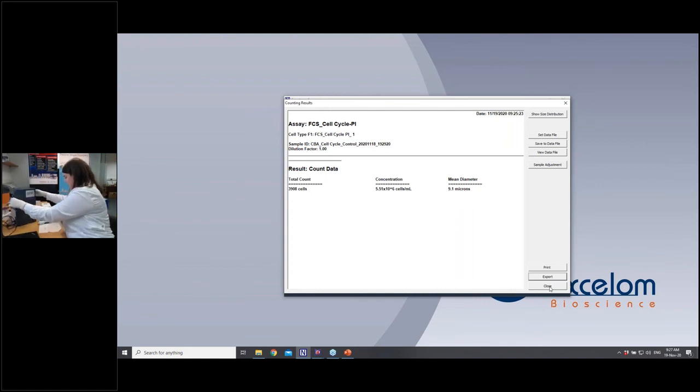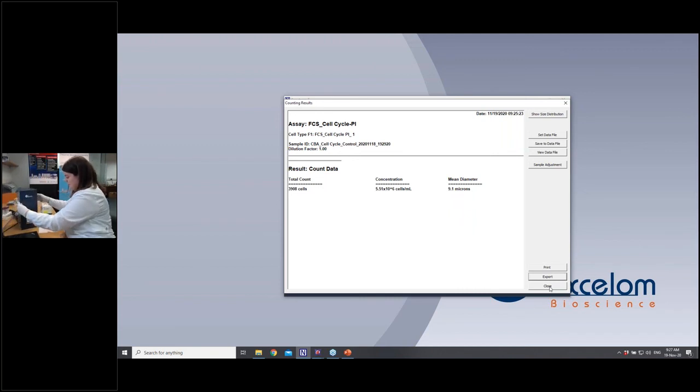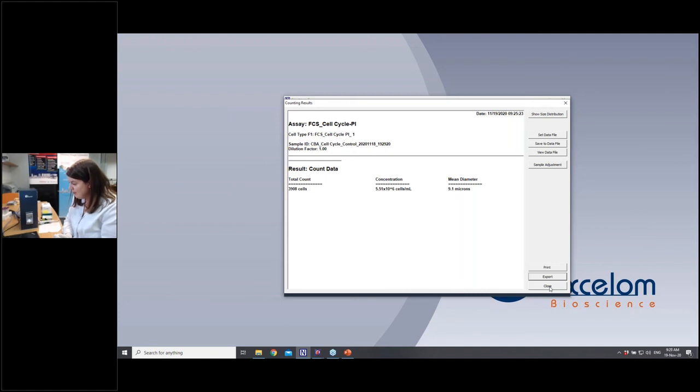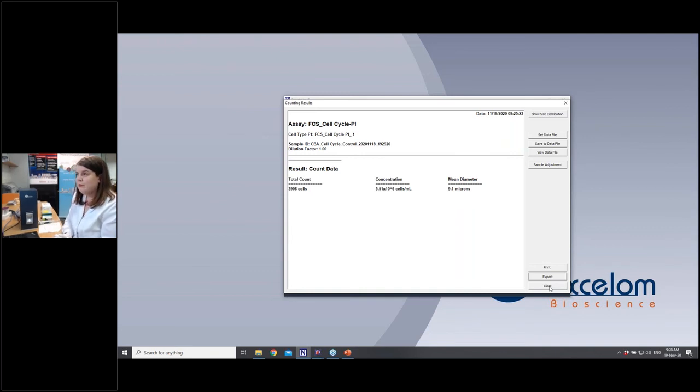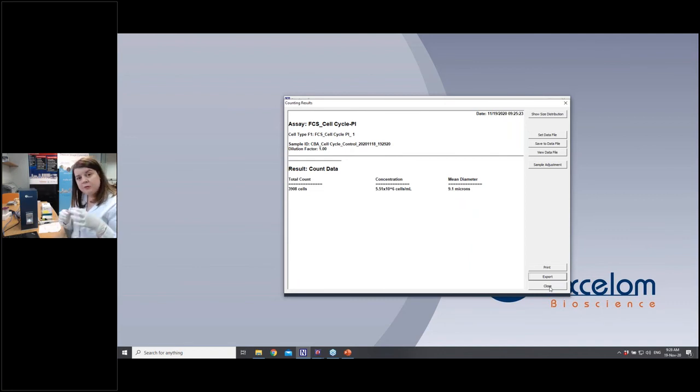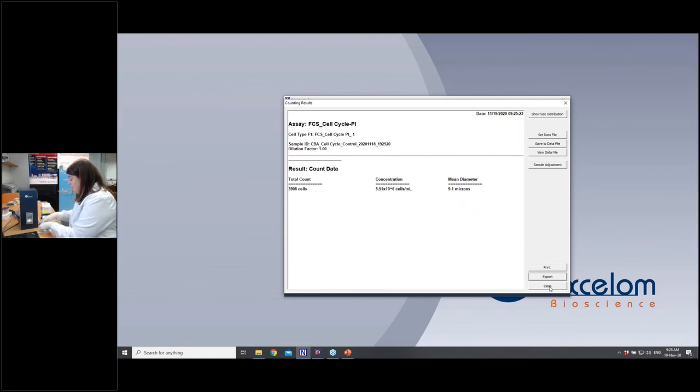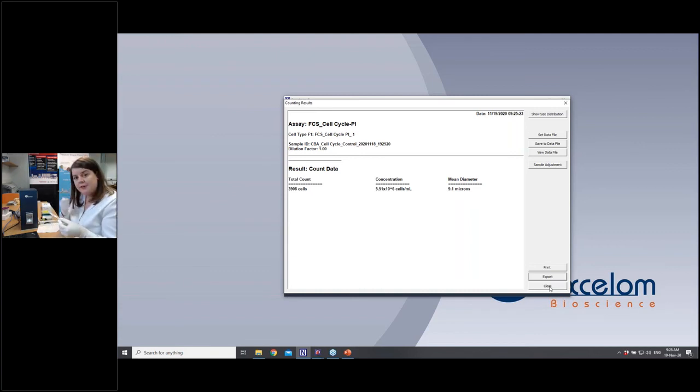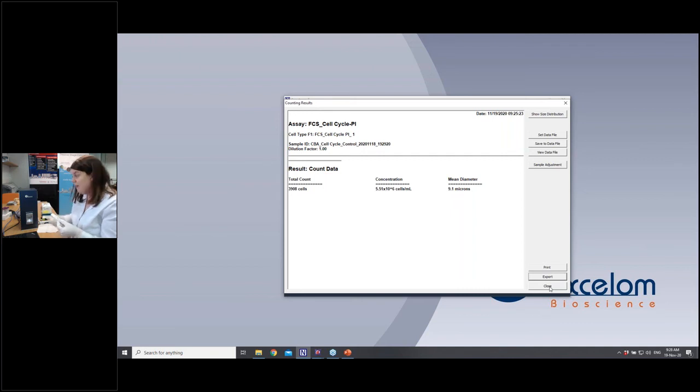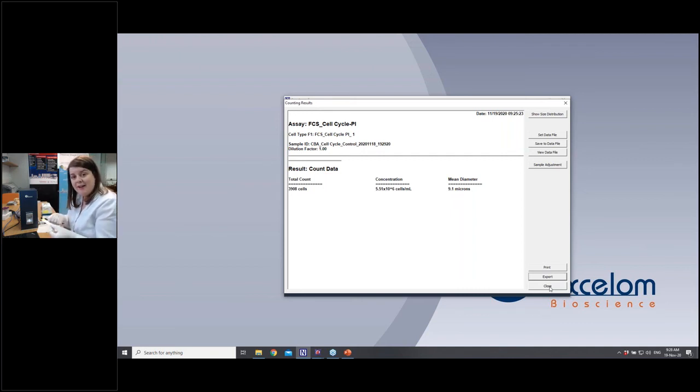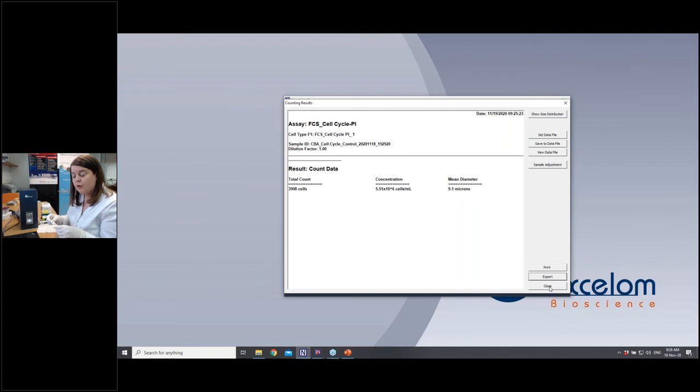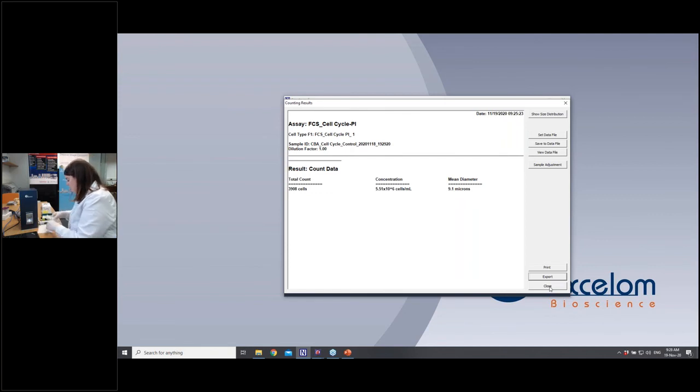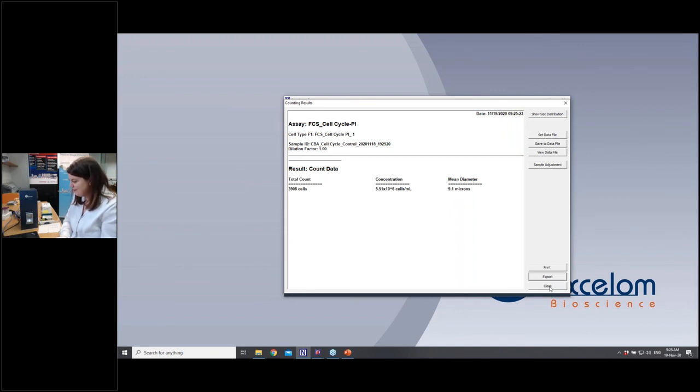Perfect thank you. I think this one kind of goes hand in hand. You showed some basic immunophenotyping experiments in your demo. What if you wanted to stain more than two markers how would you do that? Yes so you can only image two at a time so say if you're doing four different markers you can have them all stained within the same sample within the same slide so you can pick your 20 microliters into here and you can scan using your first two filters for your first time and then just simply swap them for your next two and scan again and you can do some fancy work in overlaying those images to actually get four channels four fluorescent channels if you're doing really more advanced immunophenotyping.